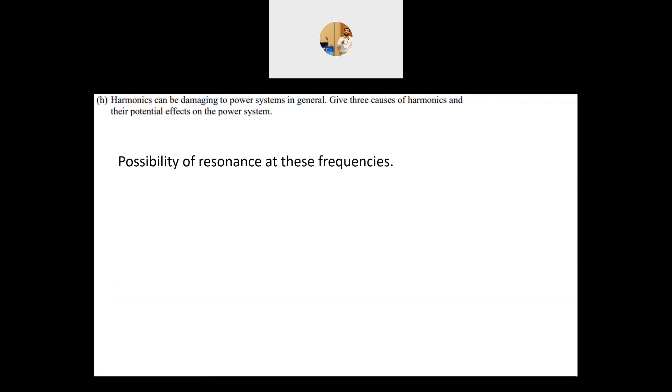The third effect is the possibility of resonance at these frequencies. When you design a system, the power system is basically inductive—you have overhead lines or underground cables, and you have the capacitance of the capacitor banks. Underground cables also have their own capacitance. So you have a mix between transformers and capacitors that might lead to resonance.